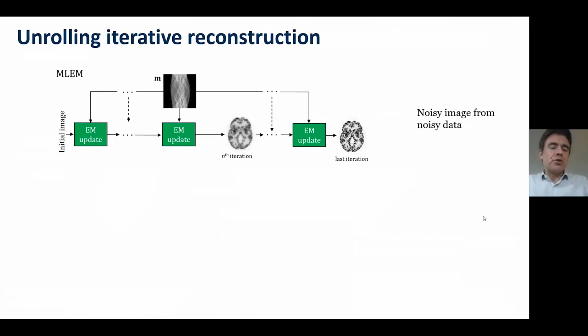Okay, but what I focus on is more elegant solutions whereby we embed deep networks inside the image reconstruction process. So in the closing minutes, I'll touch on how we do that. So at the top of the screen there, I've got the vanilla OSEM MLEM reconstruction just represented as a cascade of operations. That's how you need to be thinking about deep learning AI. Always dealing with it like a program. It's just a sequence of steps, sequence of layers. You go from input to output. So our conventional MLEM reconstruction is an initial image going through a series of steps.